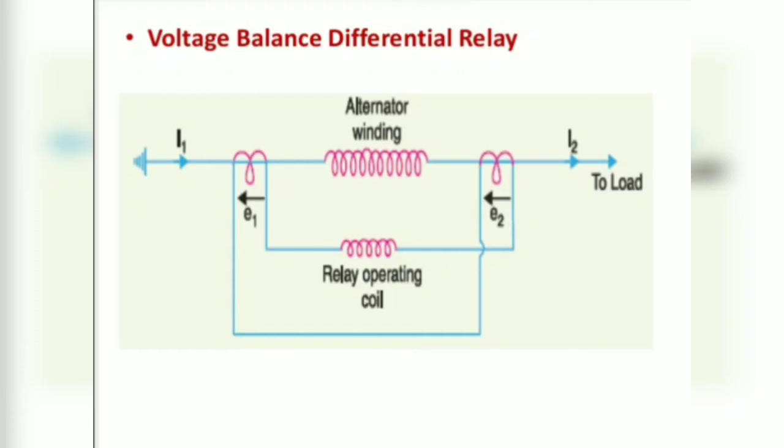The secondaries of the current transformers are connected in series with a relay in such a way that under normal condition their induced EMFs are in opposition.